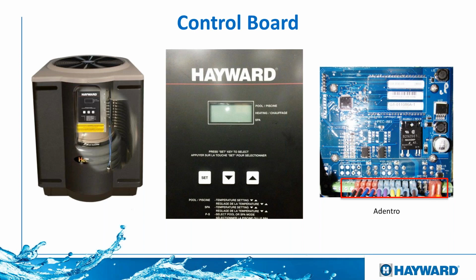Then we have this black and brown wire. That is not low voltage. This is the only exception. That's high voltage, 115 volts. That is to turn on your fan. So if we have a fan that is not coming on when it's supposed to be heating, we can take a look there, make sure that we have 110 going out, and otherwise troubleshoot the fan or the capacitor.